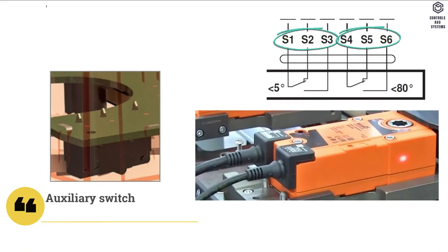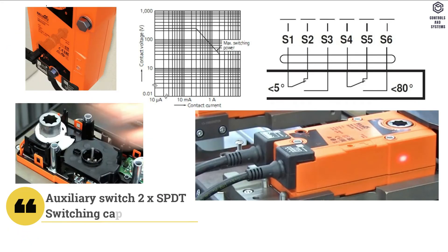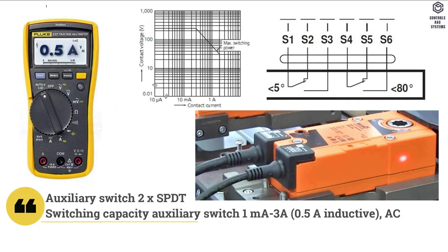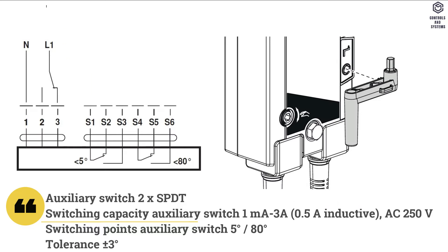2 SPDT auxiliary switches available. Switching capacity auxiliary switches 1 milliamp to 3 amps, 0.5 amps inductive, at AC 250 volt. Switching points auxiliary switches 5 degree and 80 degree.